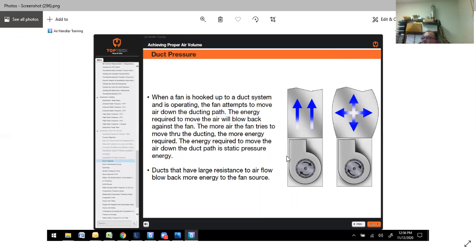Duct pressure. When a fan is hooked up to a duct system and is operating, the fan attempts to move air down the ducting path. The energy required to move the air will blow back against the fan. The more the fan tries to move air through the ducting, the more energy is required. The energy required to move air down the path is static pressure energy. Ducts that have the largest resistance to airflow blow back more energy to the fan source. So it kind of gives you a little idea here. The straight-up one is nice and smooth. This one right here is going up and down, side to side. You want it to be a nice, smooth path.